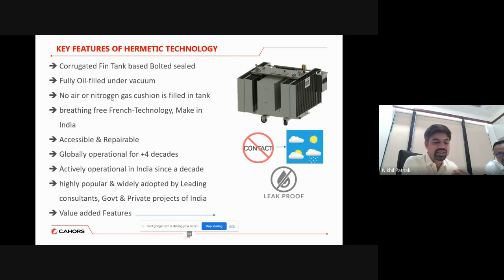I'm not saying that conventional transformers are always leaking. It depends on the build quality, the manufacturing process and the design standards of the particular manufacturer. However, the probability cannot be ignored in the case of any conventional transformer because of the detachable parts and accessories like radiators, conservator, Buchholz relay and many other things. Whenever more and more joints come into the picture, the probability remains.